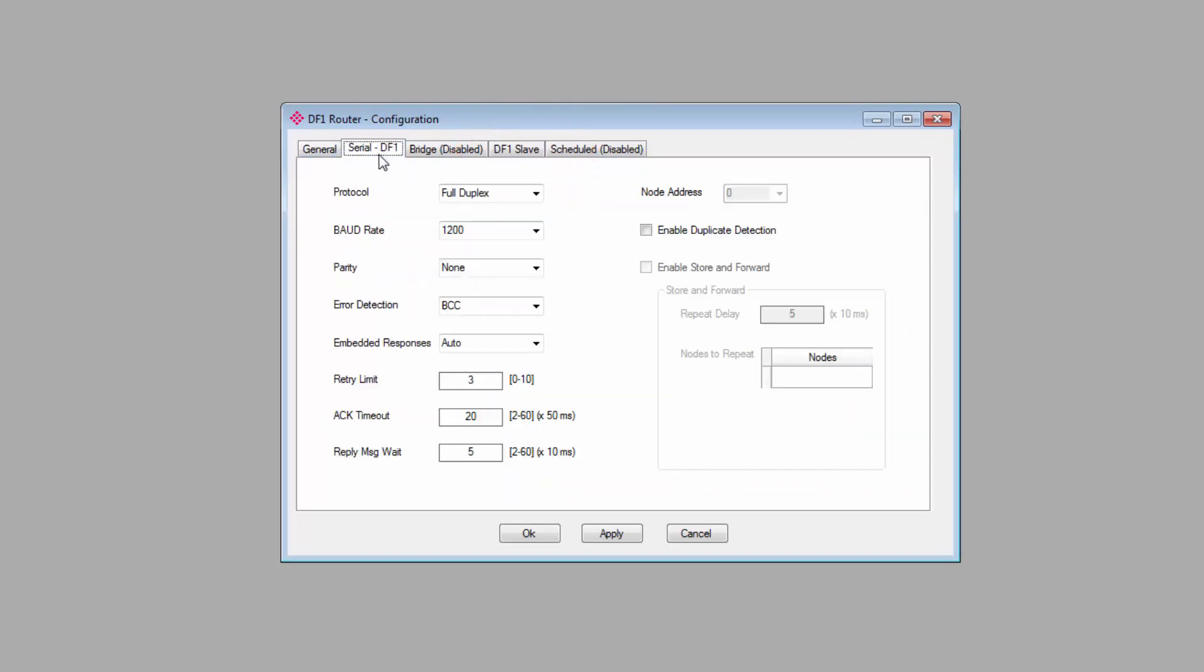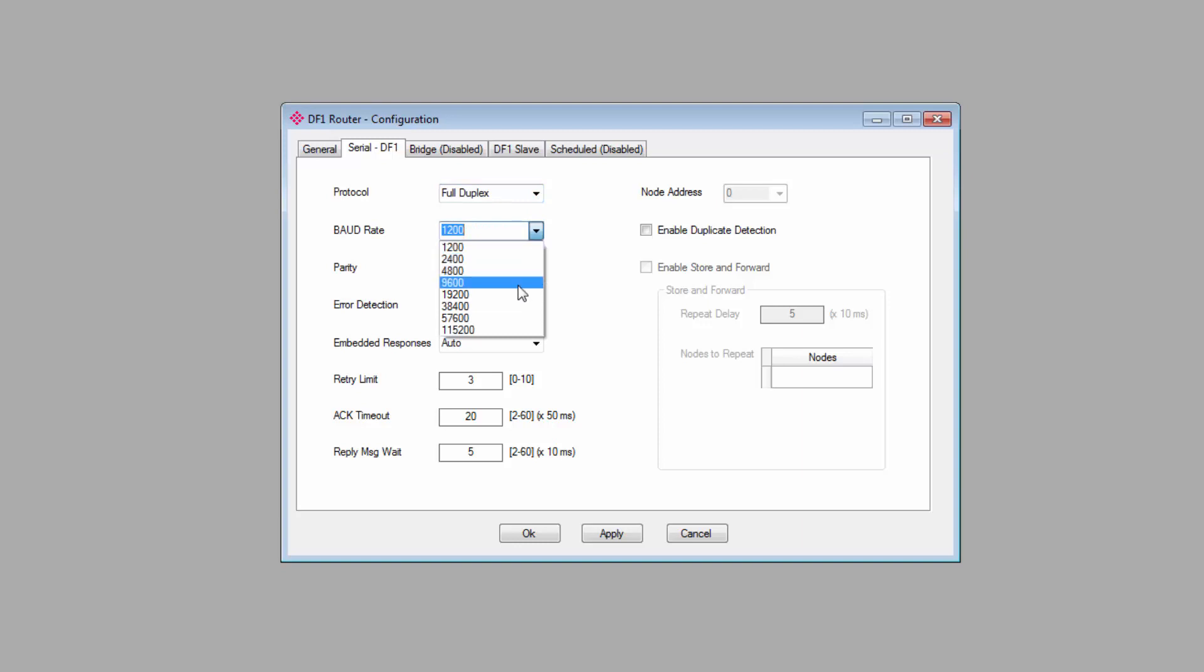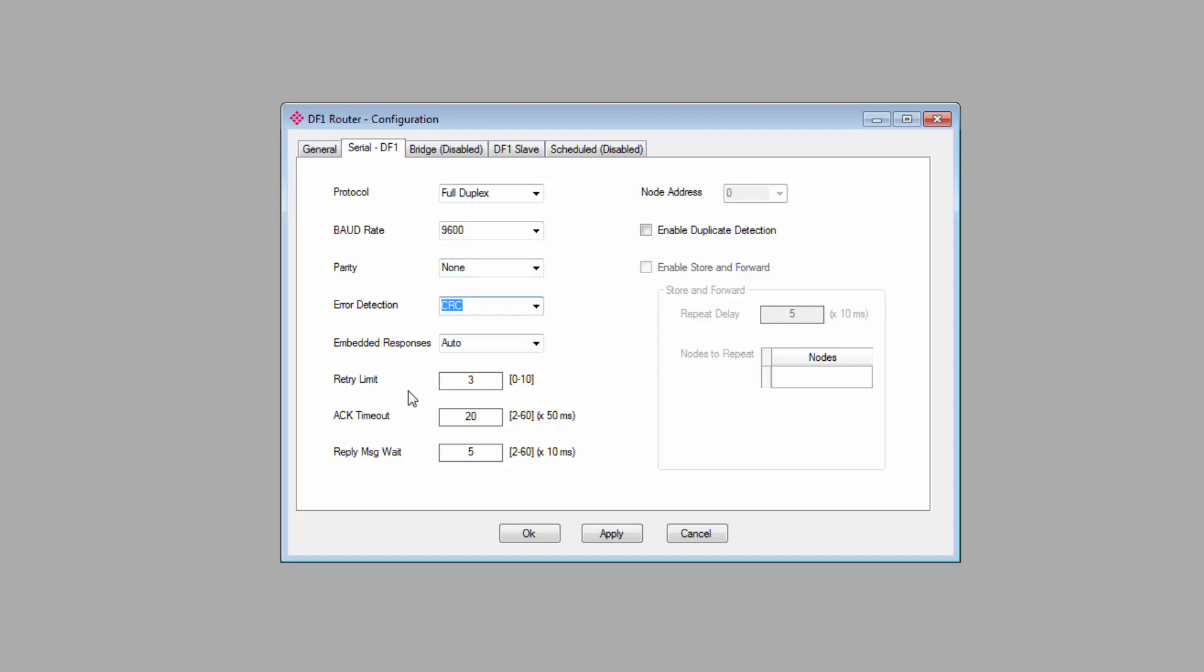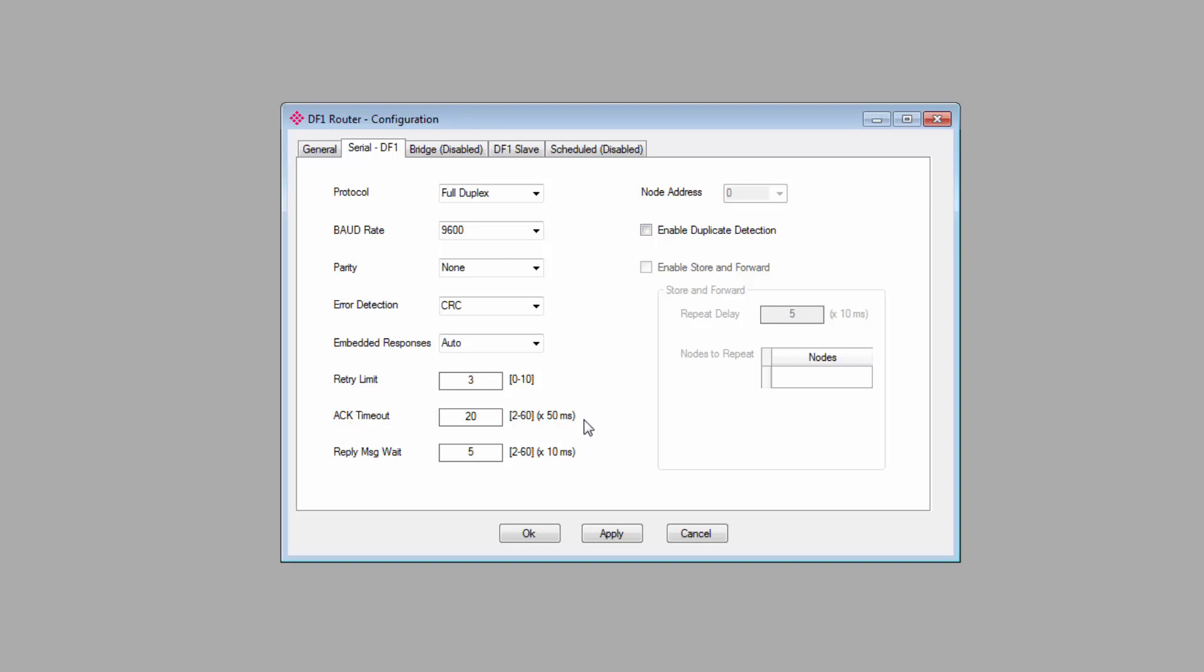Moving on, we'll click on the Serial DF1 tab. This is where we configure the DF1 side of our gateway. It contains all the typical DF1 network settings. You want everything to match the settings of the DF1 device that you're connecting to. So for protocol, I'll select Full Duplex. Baud rate will be 9600. Parity will be None. I'll set the error detection to CRC, embedded responses, retry limits, and timeouts. Just set to whatever you need. The reply message wait is intended for situations where some older legacy controllers, if the response comes back too quickly, they'll miss it. So you can add a slight delay to responses to ensure that the controller is able to process it. I'll just leave it at 50 milliseconds. There are a few other options available. Node address is relevant for certain modes, where it's possible for the module to appear as more than one node. Enable store and forward is only relevant if you're using the DF1 radio modem protocol.